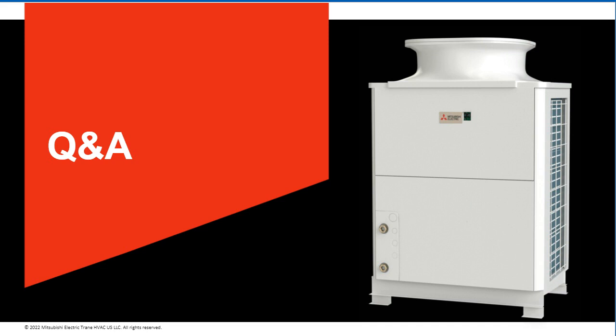All right. So we've also had a few people ask about recirculation in the building. And specifically, is the swing tank needed if there is no recirculation in the building? So I guess I'll tackle that one. If you don't have recirculation in the building, then no. You wouldn't need the swing tank, but anytime you do have recirculation, we want it there so that we don't get mixing back in the main storage tanks, which would then greatly decrease the overall efficiency of the heat pump system. But if you didn't have recirc in the building, you could do it without the swing tank.